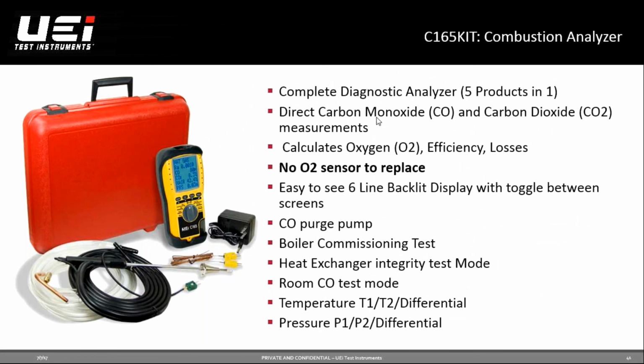One of the other really nice features is the boiler commissioning test, which is a pre and post test that walks you through it step by step. It's very popular in the UK, and it follows the exact same startups that boiler manufacturers ask you to do. I like it because it tells you step by step - insert the flue probe, hit enter, wait until it steadies out, hit enter - and it walks you through every section.